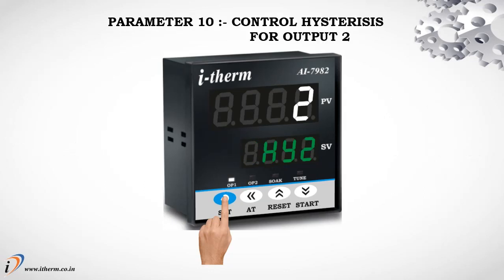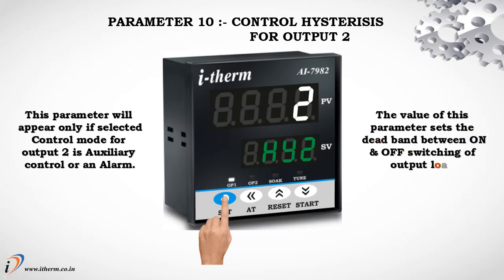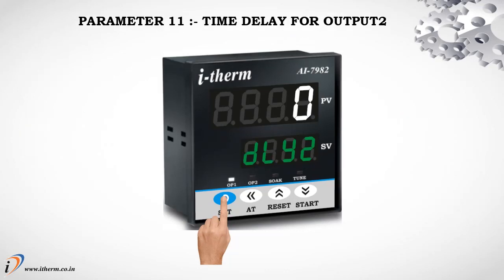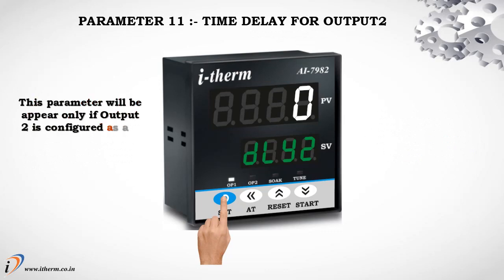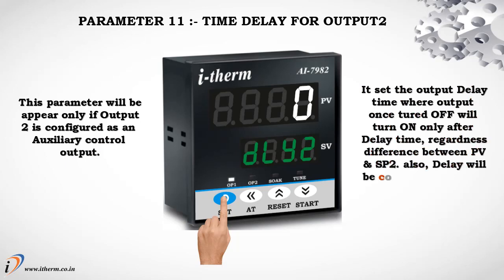Parameter 10: Control hysteresis for output 2. This parameter will appear only if the selected control mode for output 2 is auxiliary control or an alarm. The value of this parameter sets the dead band between on and off switching of the output load. Parameter 11: Time delay for output 2. This parameter will appear only if output 2 is configured as an auxiliary control output. It sets the output delay time where output, once turned off, will turn on only after the delay time, regardless of the difference between process value and set point 2. Delay will also be considered at every power on.